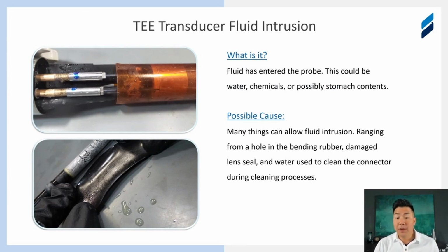So we've been talking about fluid ingress into TEE probes, and here are just a couple of examples of fluid getting inside and running up and down the probe, depending on how it's stored. Let's start with the bottom. We opened up this bending rubber here, and you can see that this had some pretty catastrophic fluid ingress. It literally is just spewing out of this bending rubber. So with those punctures, there's a lot of fluid that can get in there. It doesn't seem like much, but just one drop will cover dozens of circuits and short them all together all at once.